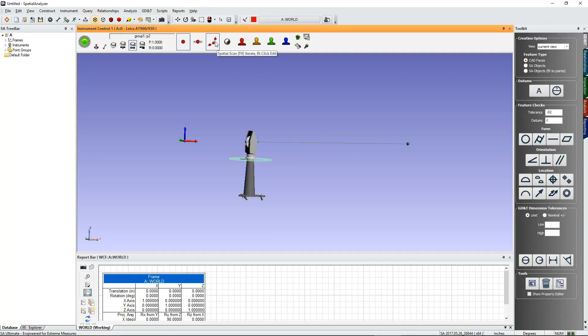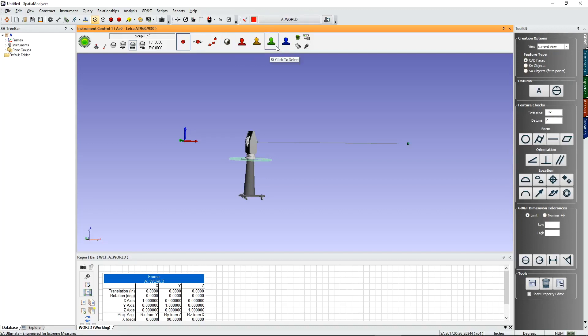The third profile is Spatial Scan, which takes a continuous stream of points and also has a stable start trigger that waits for you to stabilize before beginning the stream. The fourth is Tooling Ball — select this and SA will let you take several points around the outside of a tooling ball, construct the sphere, find the center, and return just that single center point instead of a dozen or more individual points, saving significant time when tying into tools with many tooling balls.